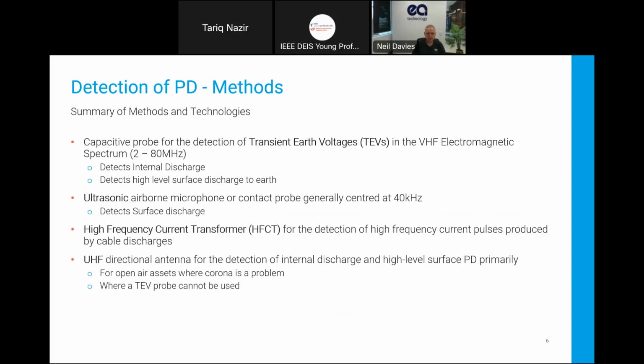So transient earth voltages, which will be working in the 2 to 80 megahertz region typically. And that's very good for detecting internal discharge, and it will also detect high-level surface discharge to earth. When we're talking about surface discharge, because we get a relatively low spark of energy, then we may not get enough to generate these high electromagnetic pulses that we can detect using the TEV method, the transient earth voltage method.